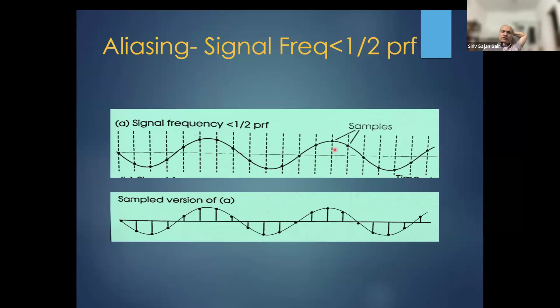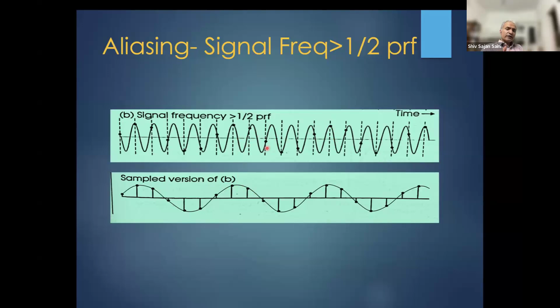But if the frequency of the signal is very high, and we know our pulse repetition frequency is the same, so now the signal frequency is increased. Now it is going to cut this at this particular point. This pulse is going to cut the signal at this particular point, and so on. And once we join the dots, the Doppler shift is very different from the frequency of the signal. Because it is very different, there is a loss of signal. There is a loss of data. Now, this loss of data is represented on a screen as aliasing.